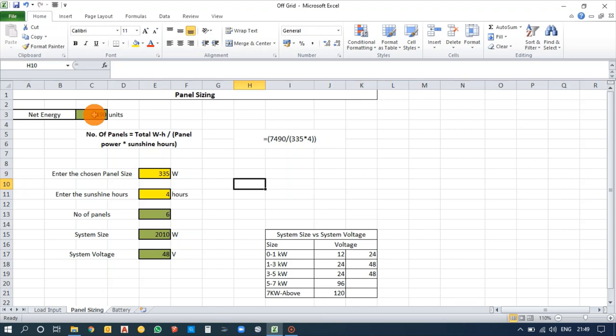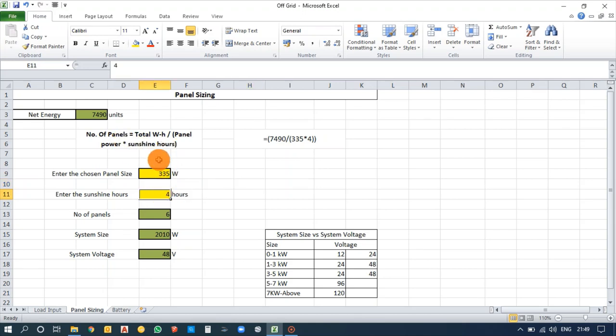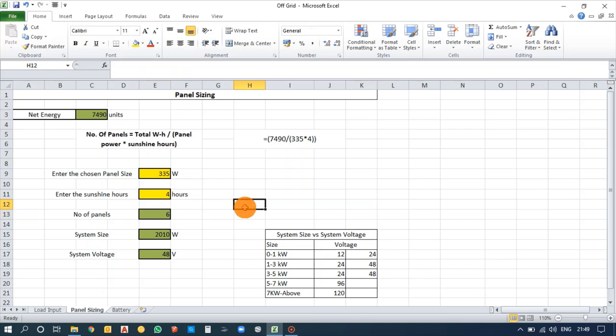For panel sizing, take the net energy you calculated and choose a panel model — I have chosen a 335-watt panel. The formula uses total watt-hours, panel power, and peak sunshine hours (taken as 4 hours). Equating this gives 6 panels. The system size comes to around 2 kilowatts, and the inverter voltage selected is 48 volts.